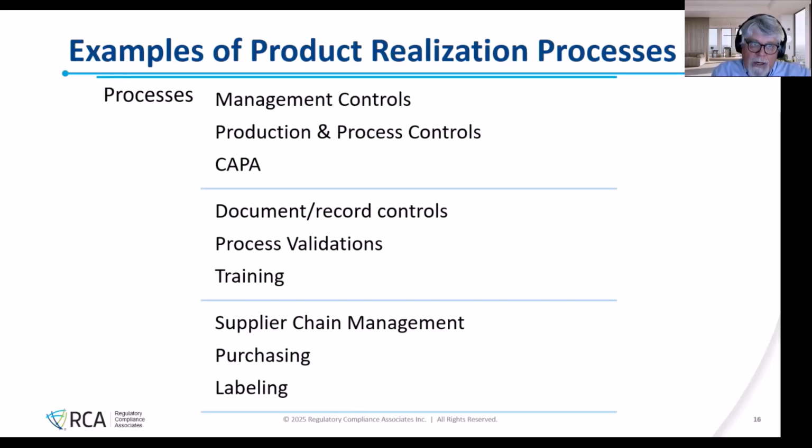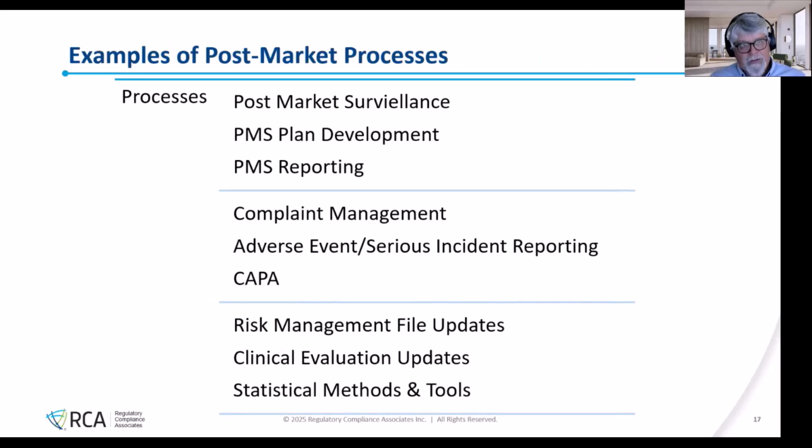So we've covered pre-market, product realization. Now we're going to sell the product and put it out in the market. And this is post-market. From an EU MDR perspective, post-market surveillance is on steroids. They really ramped it up, and so we have to pay attention to that and the different reports that they're going to want done. So we have post-market surveillance, which means keeping an eye on the product, ensuring that your product is still safe for intended use and has effective performance. You're going to have a post-market surveillance system. Within that, you're going to have a post-market surveillance plan, development, and reporting.